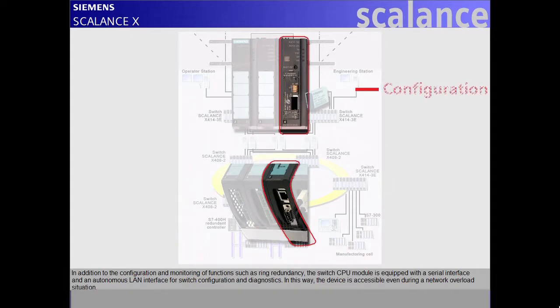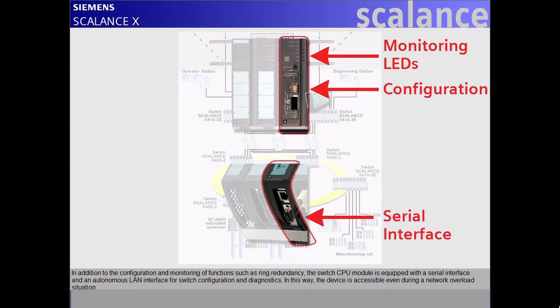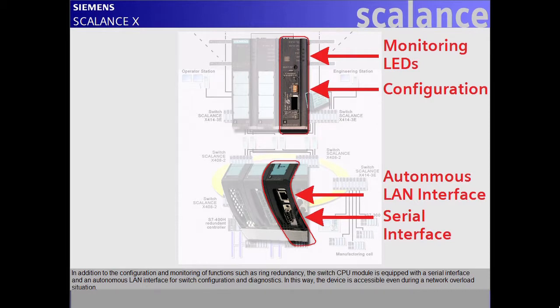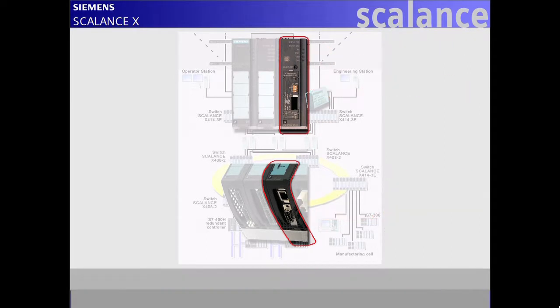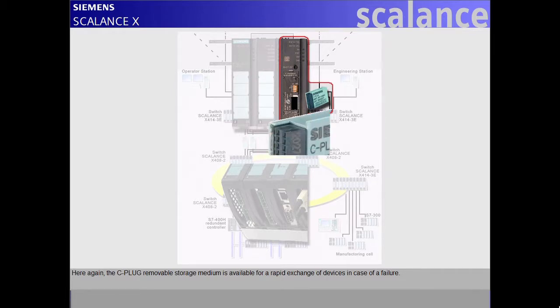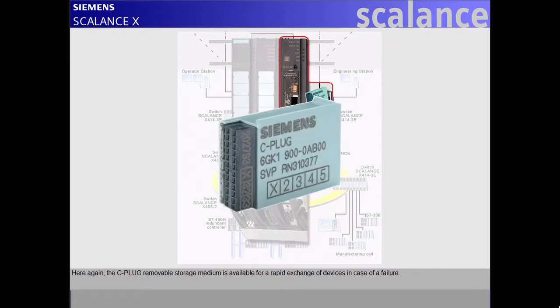In addition to the configuration and monitoring of functions such as ring redundancy, the switch CPU module is equipped with a serial interface and an autonomous LAN interface for switch configuration and diagnostics. In this way, the device is accessible even during a network overload situation. Here again, the C-plug removable storage medium is available for a rapid exchange of devices in case of a failure.